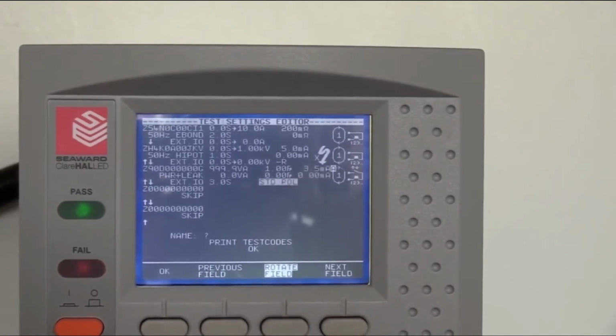Finally, again, we can set whether we want the polarity to be standard, as in mains in and out. We can also reverse the polarity if your standard calls for reverse polarity tests. But for today, we're just going to perform it at standard polarity. We know the incoming mains on our circuit here for today is correct. The live and neutral are in the correct orientation. So we'll perform the test in a standard polarity. In some routine tests and some conformance tests, it is a requirement that you switch between standard and reverse polarity. If you do have to do that, the HAL can sort that for you.